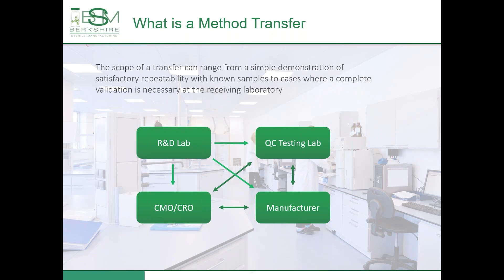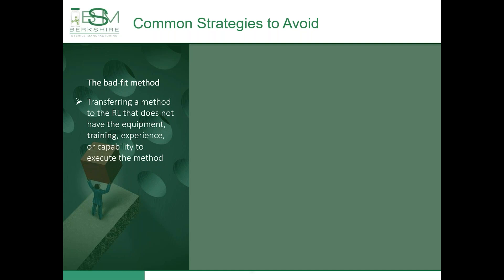Let's start off with some common strategies to avoid. The bad fit method: transferring a method to a receiving laboratory that does not have the equipment, training, experience, or capability to execute the method. If the receiving laboratory needs to purchase an instrument to qualify and transfer a method, time needs to be built into the schedule to purchase, qualify, and train on the use of the new instrumentation. Bad fit methods can also include limited access to critical reagents, such as standard materials, as well as reagents used to execute the method and prepare solutions. When reagents are in critical supply, that leaves a lot of pressure on the receiving laboratory to execute right first time, without allowing opportunity to train individuals on the method or instrumentation.